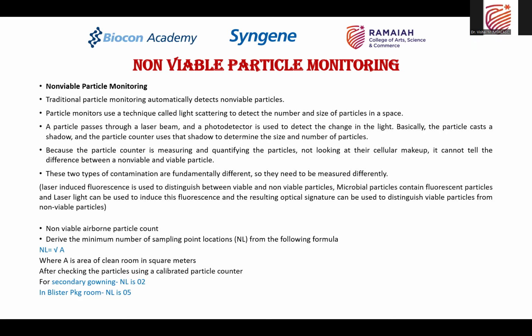So it cannot differentiate between viable and non-viable sometimes. Now, to overcome this problem, the fluorescence-induced laser beam is used. This fluorescence-induced laser beam can differentiate between viable and non-viable particles. Now, how will this fluorescence differentiate between viable and non-viable particles?